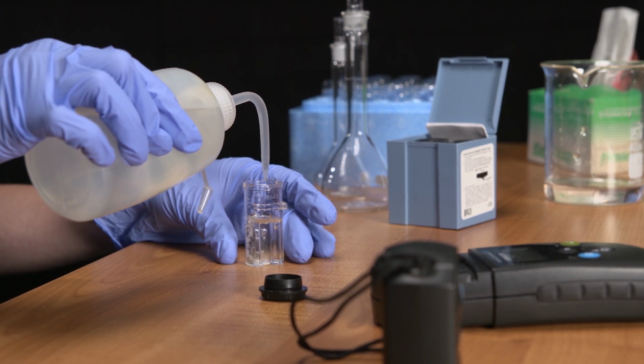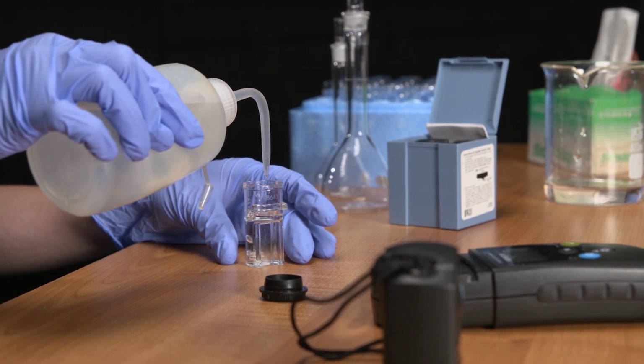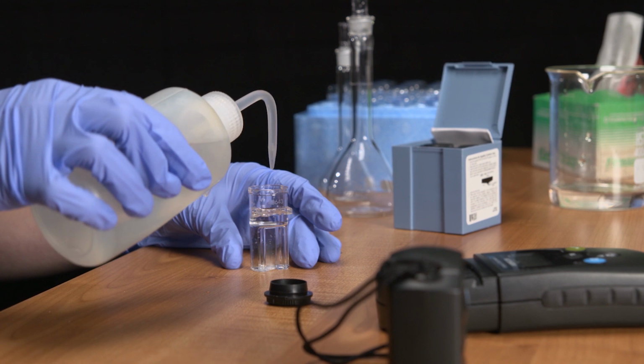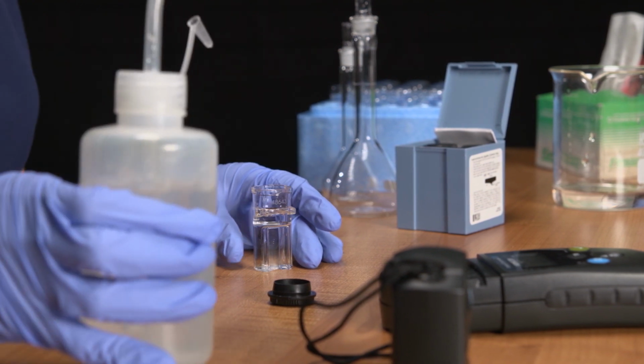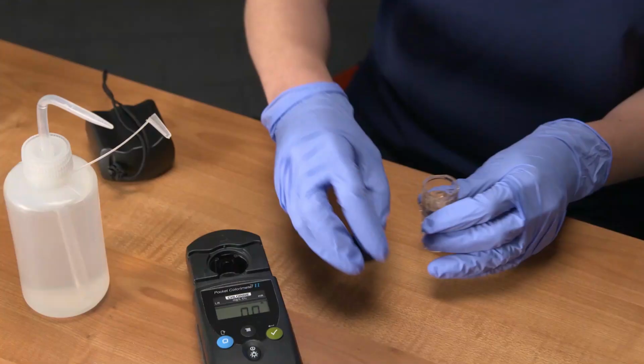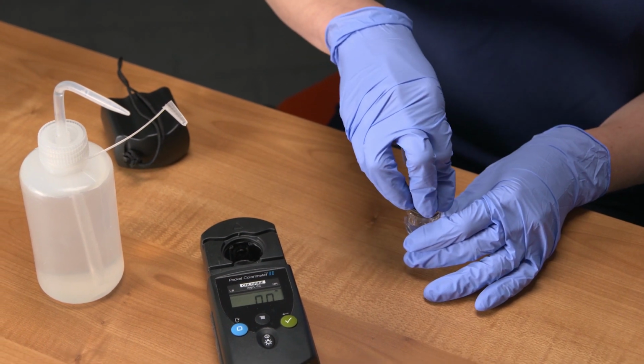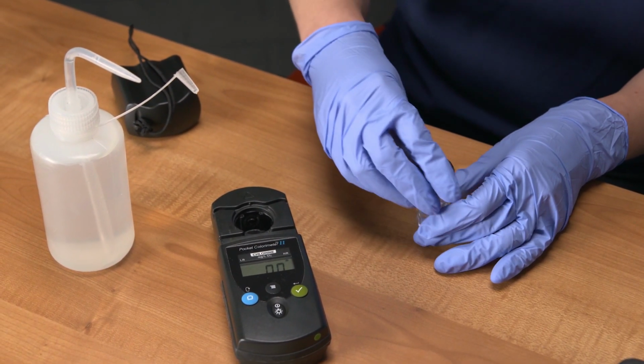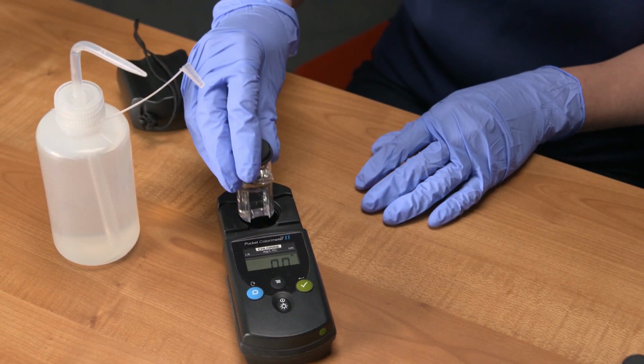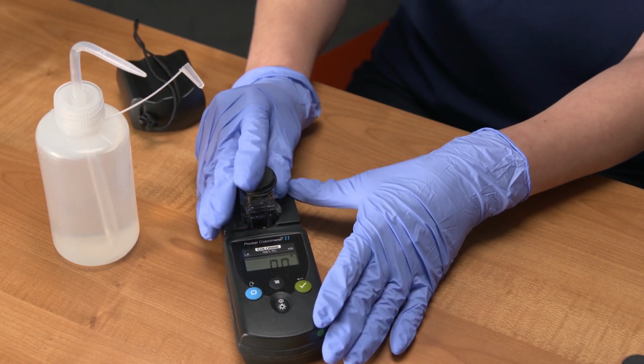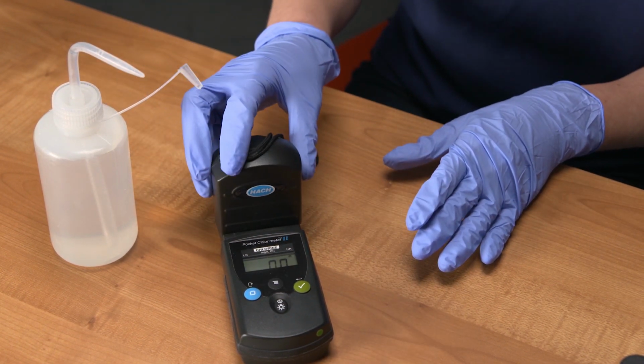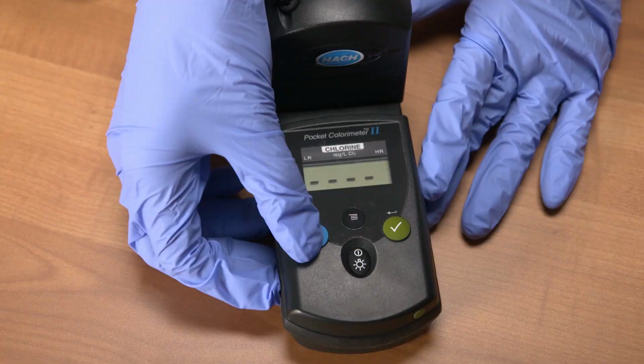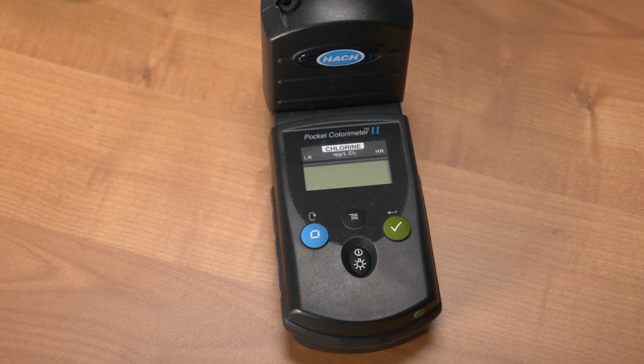We will fill a sample vial with purified water. First, ensure the vial is not scratched or stained, and rinse several times with reagent water. We wipe the vial with a lab wipe to remove any fingerprints. Place the vial in the instrument, align the vial according to manufacturer recommendations, place the cap over the sample vial, and then push the 0 button. The display should read 0.0.